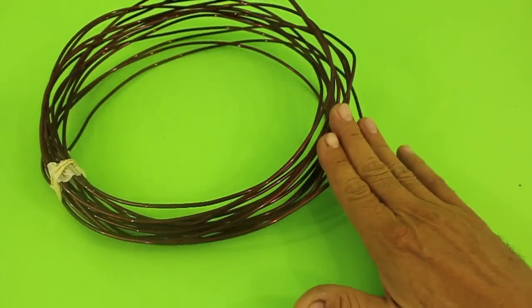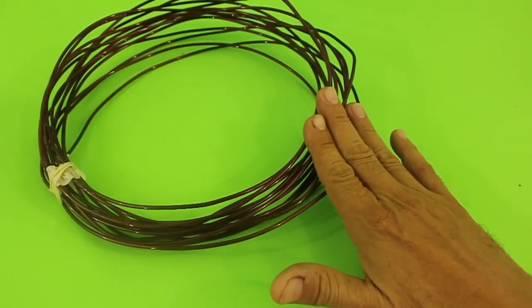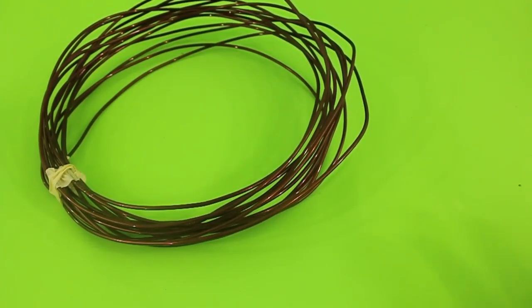This for example is size 10 AWG. There are tables of copper wire that give you all the parameters of the wire. You can see that for size 10 the wire has a resistance of 0.9989 ohms for every 1,000 feet of length.